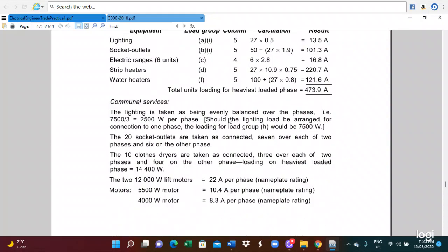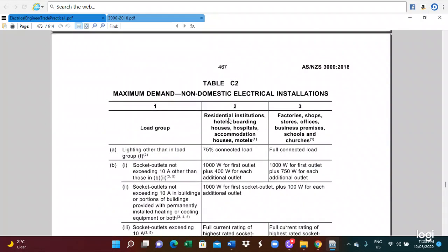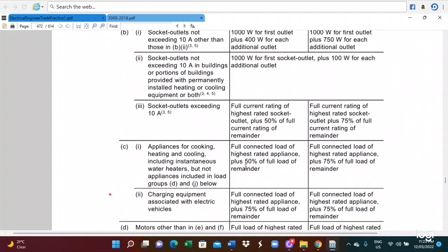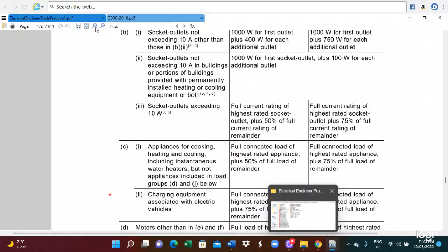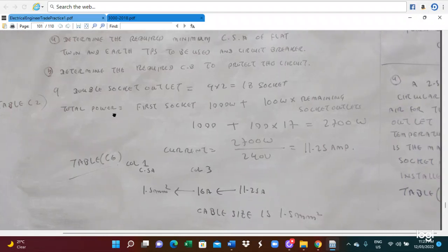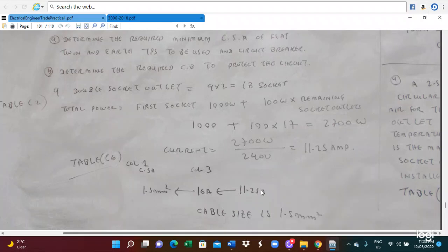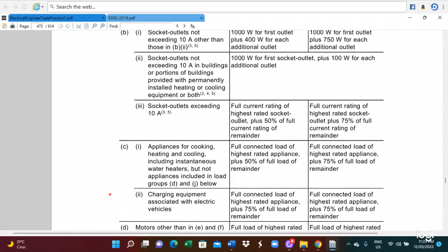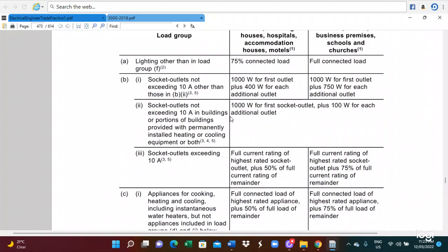Table C2 of the AS3000 rule. So total socket outlet gives total power, using table C2 of AS3000. The rule states: for socket outlets not exceeding 10 amperes, it's 1000 watts for the first socket outlet and 400 watts for each additional socket outlet. This is the rule we have to utilize.